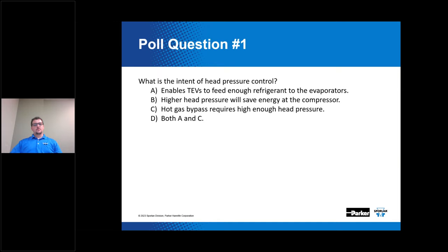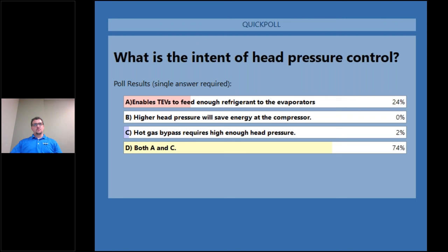The majority got this correct. The answer is D — both A and C. 74 percent chose option D correctly. Only 2 percent chose option C alone, and 24 percent chose option A — which enables thermal expansion valves to feed enough refrigerant to the evaporators. Both A and C are correct intents of head pressure control.